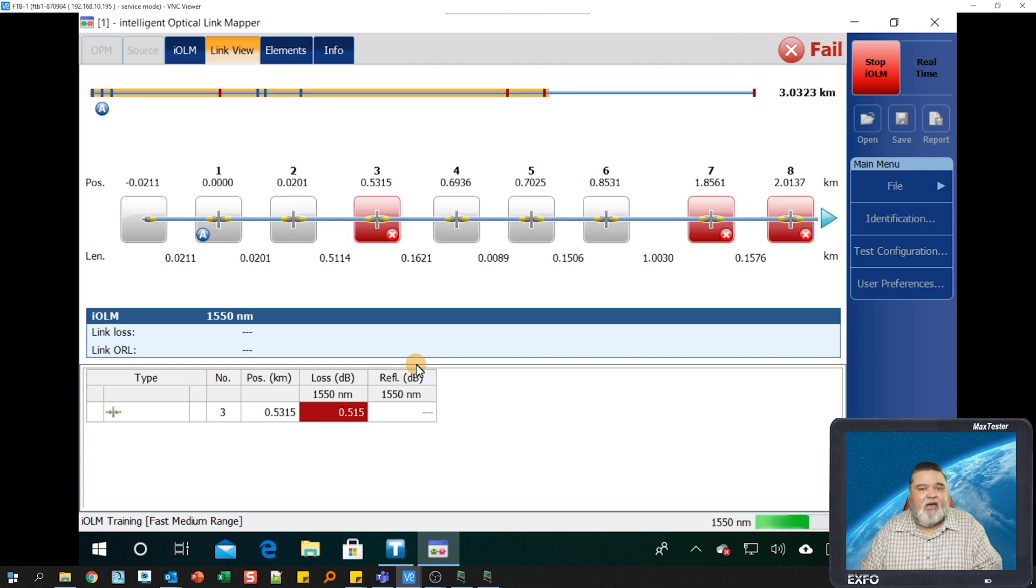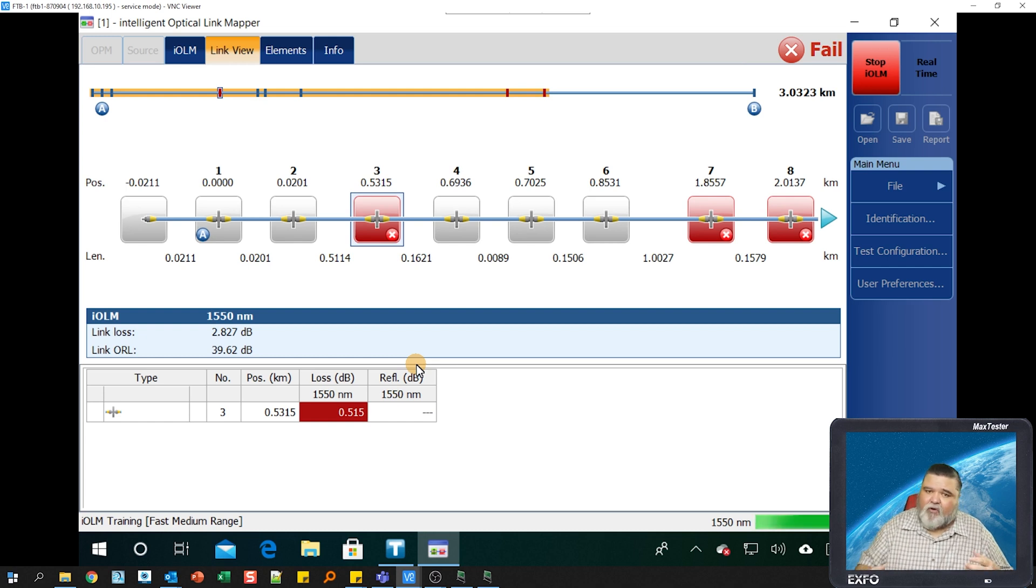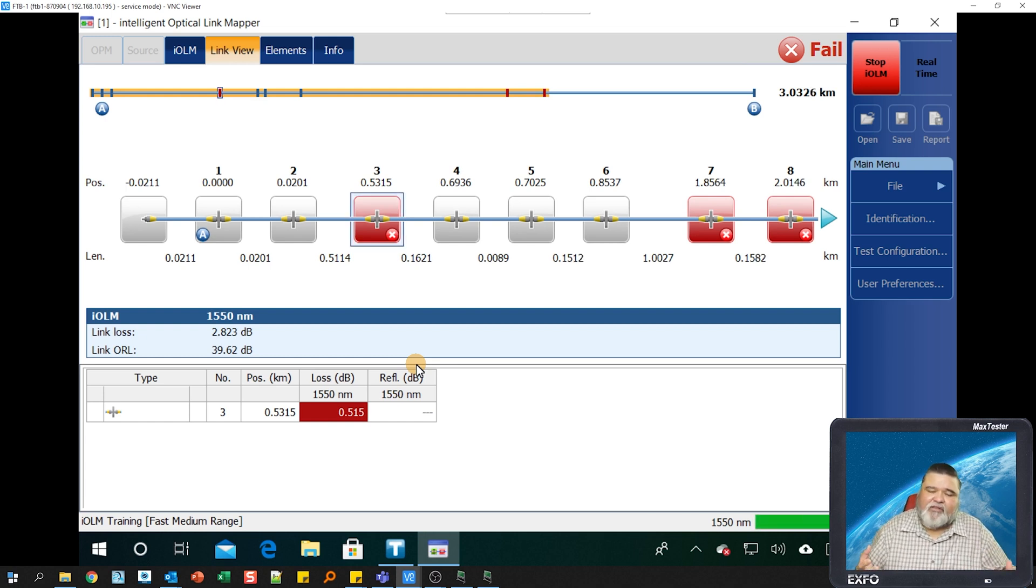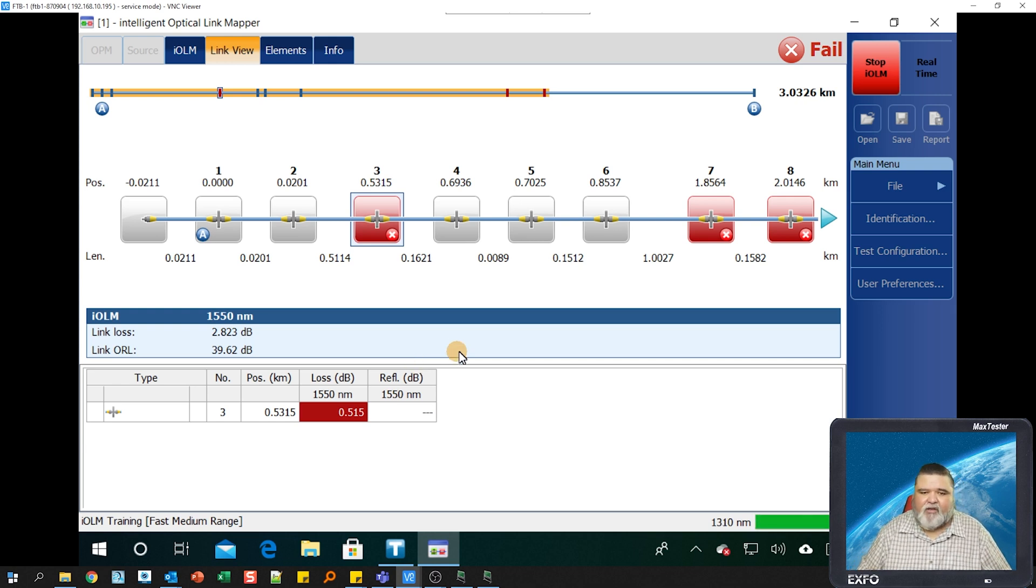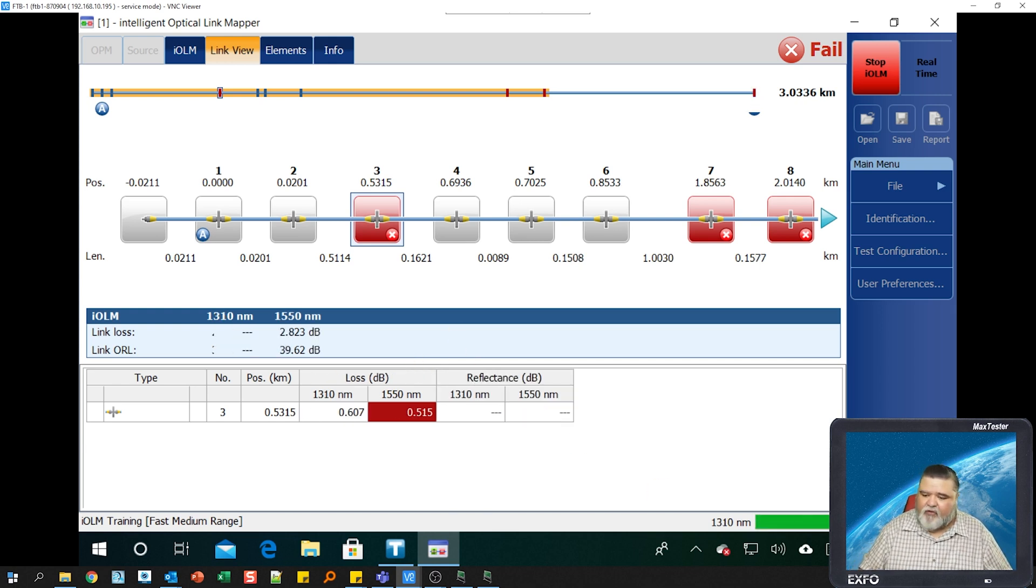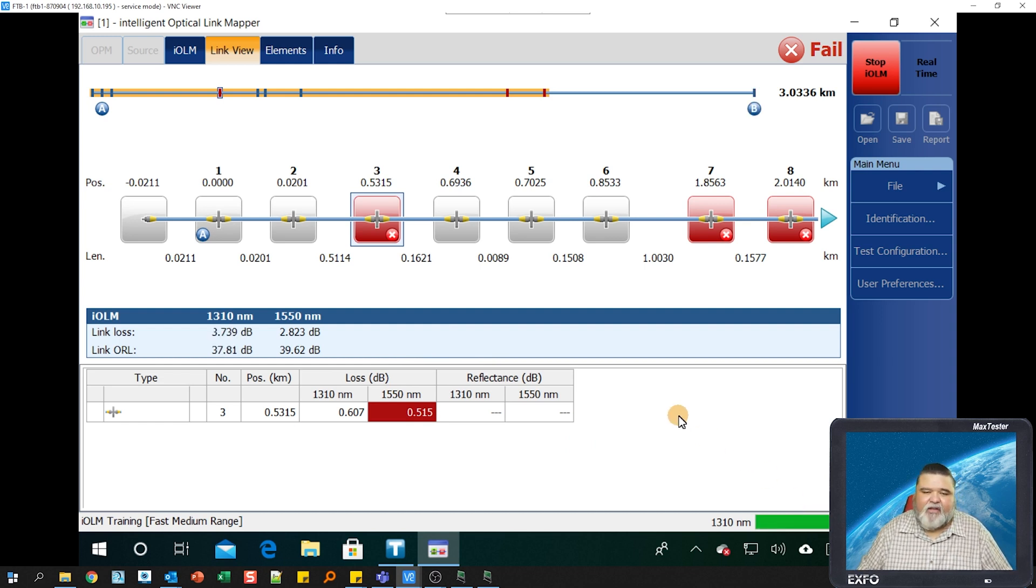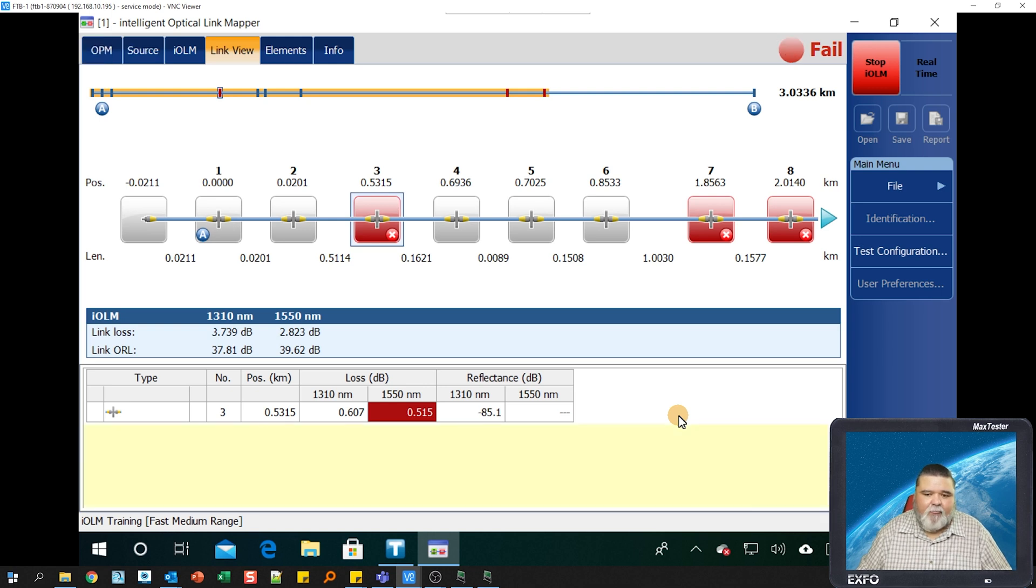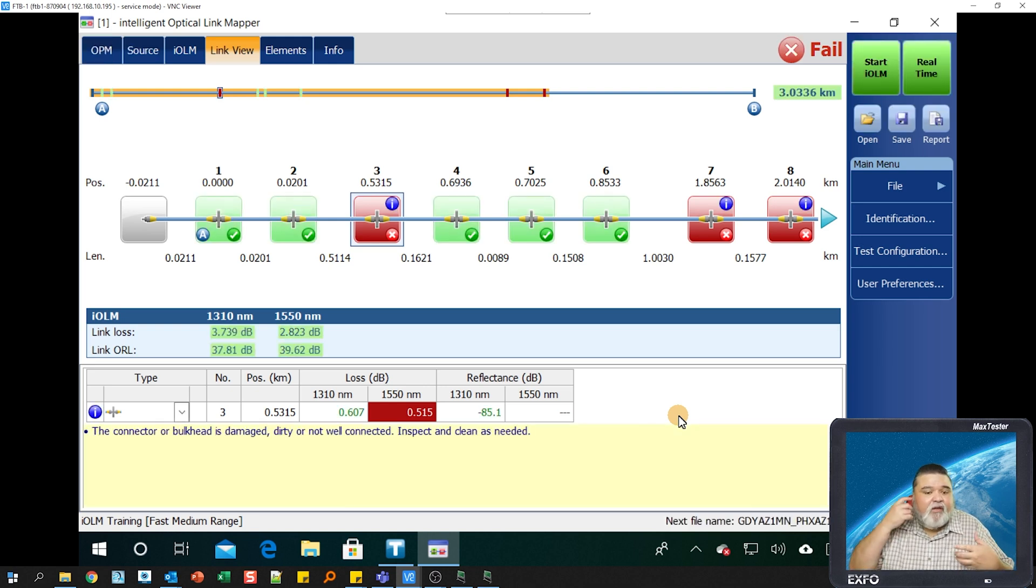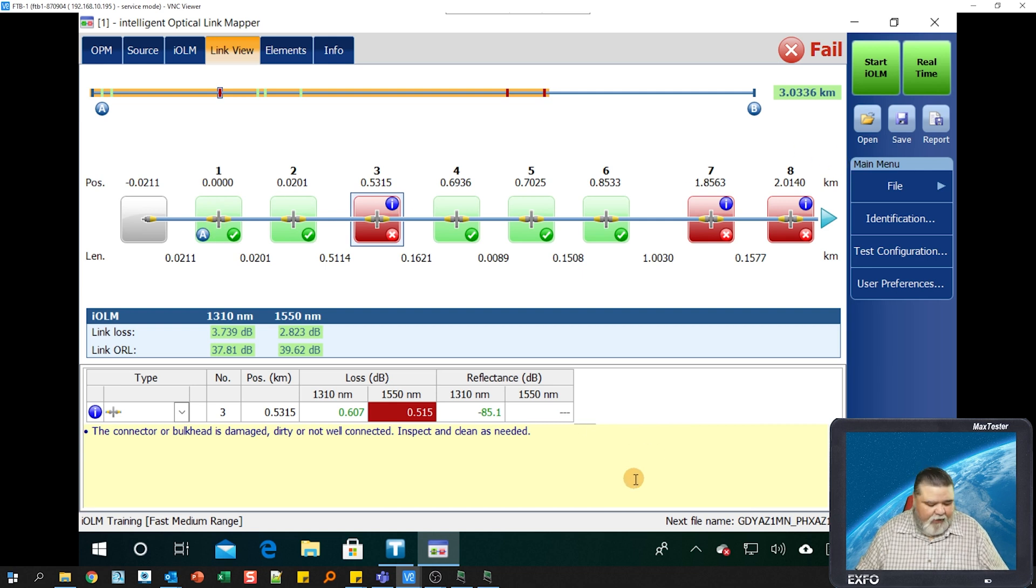I'm going to go ahead and just hit start IOLM to start the test. IOLM is going to go out there using that configuration fast medium range. It'll run out there and do a quick test. You can create different types of configurations for fiber to the antenna, fiber to the home, different test scenarios. In this case, we're just doing this one for training purposes. You'll see the status indication there on the bottom right. We'll let it go ahead and do its test.